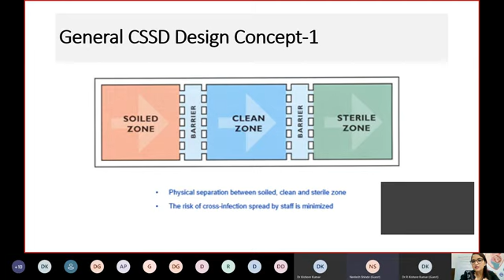And if you see, the one principle that really applies to CSSD is that the soiled and the sterile zones should never crisscross each other. That means you should not be able to move into these zones by crisscrossing. So it should always be a linear movement. But sometimes it may not be possible to have this kind of a design.